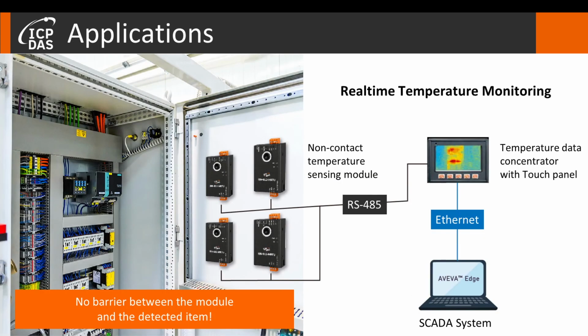As you can see on the picture, the module can detect the temperature of the power panels without touching it. It's more convenient and safer, and the collected data can be sent to the SCADA system. You can see the real-time temperature on the SCADA. If there is any problem, the engineer can go to fix it immediately.